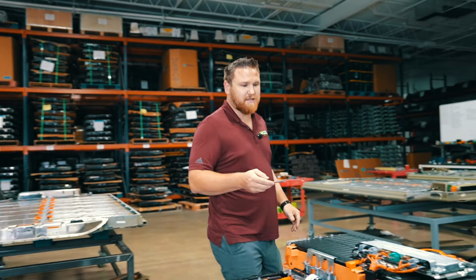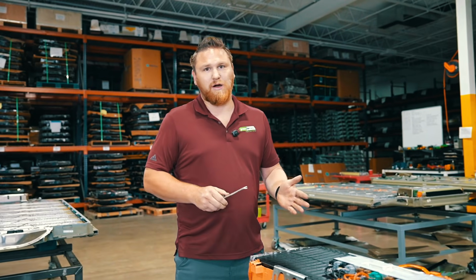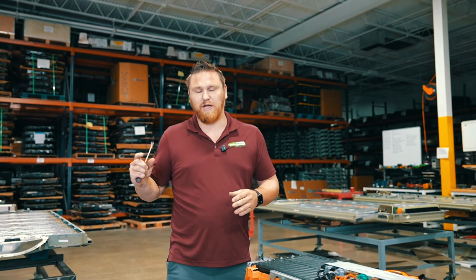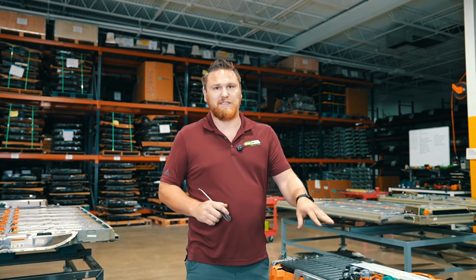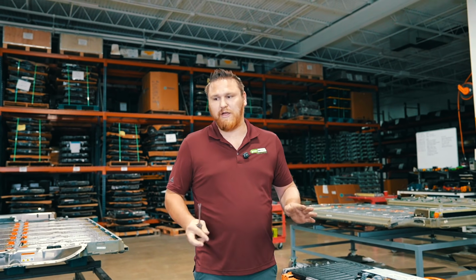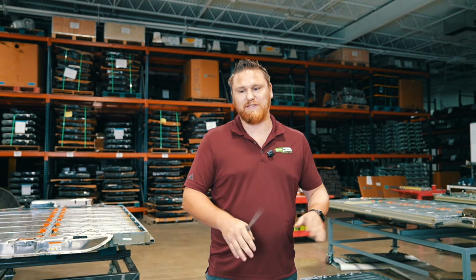We're going to start by disconnecting the BMS. That's always the first step we do. If we disconnect one module while the BMS is still active, it can cause damage to the BMS. So if you're ever doing repairs, always do the BMS first, disconnect everything on it, and then you can start doing bus bars and other harnesses.